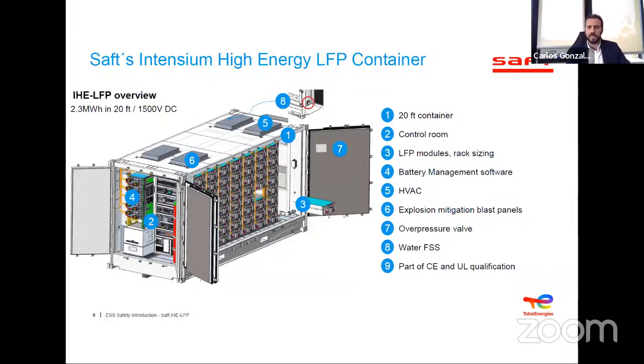In case the gas suppression has not been enough, we can activate the water FSS, which has water sprinklers directed to each module to ensure the reduction of temperature individually. As mentioned before, it's very difficult for water to reach the modules and cells from outside the container because of the many layers and enclosures, so this is how we reach the separate modules individually. We also have a water drain to remove water inside the container and reduce the chance of creating hydrogen gas by electrolysis.